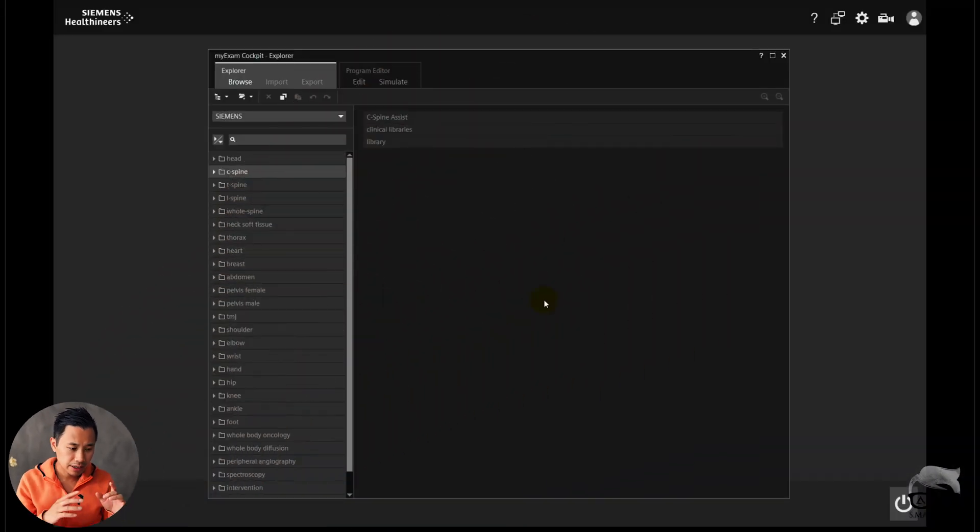But with the in-phase, I always find it somehow blurry — not sharp enough compared to a standard 2D Turbo Spin Echo. This has just changed now. Currently at the XA50 with Deep Resolve combined, I find the in-phase is very sharp now, also along with the water-only. Let me show you some images.